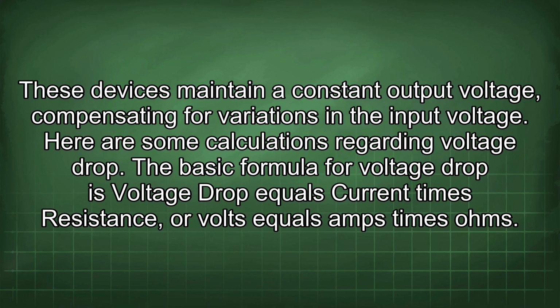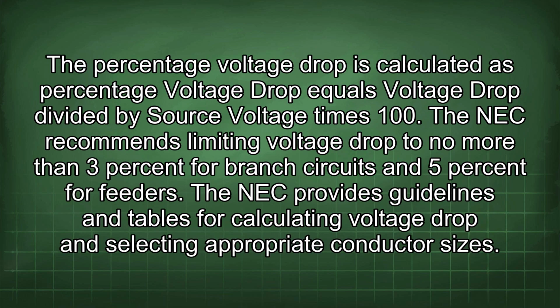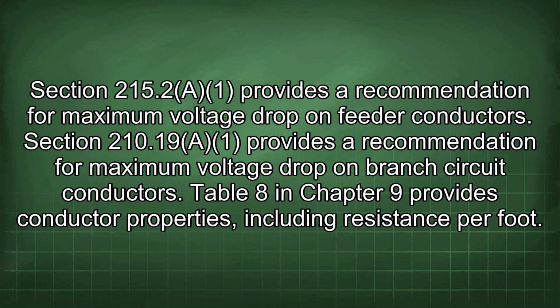Here are some calculations regarding voltage drop. The basic formula for voltage drop is voltage drop equals current times resistance, or volts equals amps times ohms. The percentage voltage drop is calculated as voltage drop divided by source voltage, times 100. The NEC recommends limiting voltage drop to no more than 3% for branch circuits and 5% for feeders. The NEC provides guidelines and tables for calculating voltage drop and selecting appropriate conductor sizes. Section 215.2(A) provides a recommendation for maximum voltage drop on feeder conductors. Section 210.19(A) provides a recommendation for maximum voltage drop on branch circuit conductors.